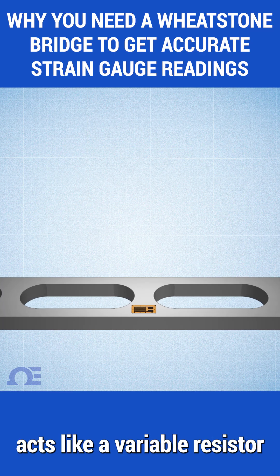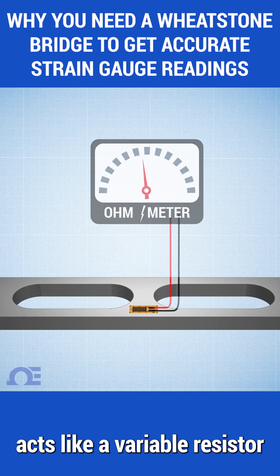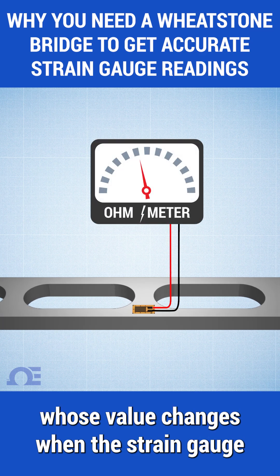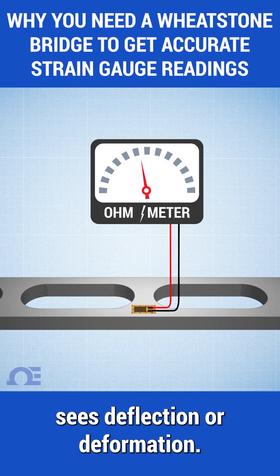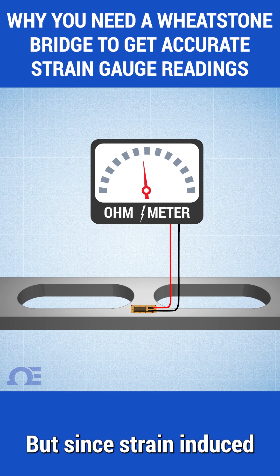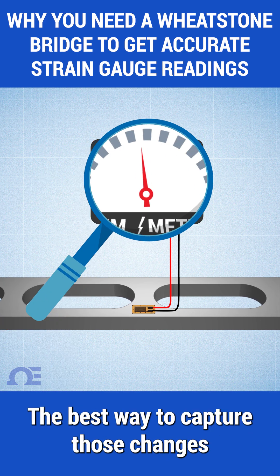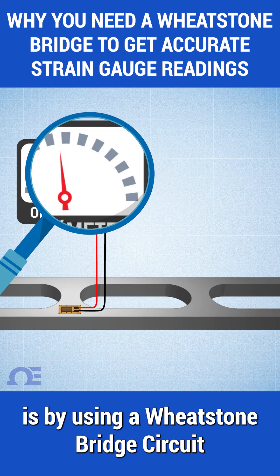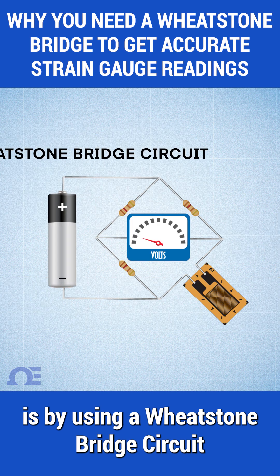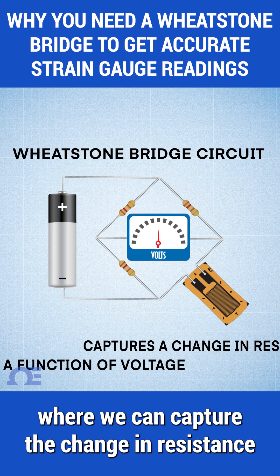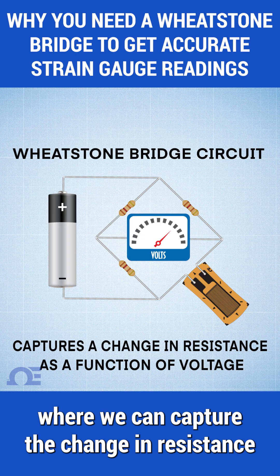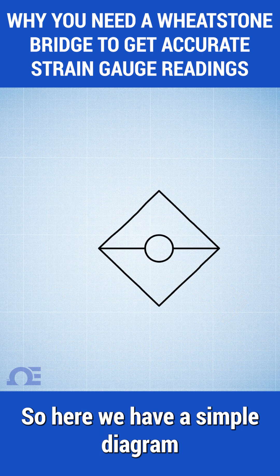A strain gauge by itself acts like a variable resistor whose value changes when the strain gauge sees deflection or deformation. But since strain-induced resistance changes are extremely small, the best way to capture those changes is by using a Wheatstone bridge circuit, where we can capture the change in resistance as a function of change in voltage.